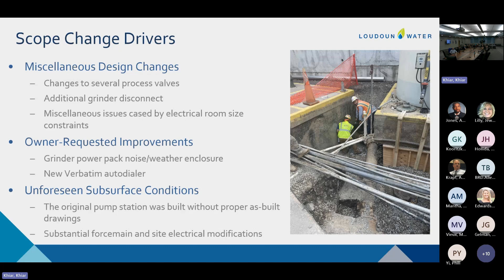To deal with this, in the case of the electrical conduit, we decided that for dealing with the issue of safety, capacity, and lack of adequate protection, the best solution would be to route from the interior panels and devices out along the retaining wall pictured in the back, hit new junction boxes, and go underground at the proper depth with proper bedding and routing, then hit the devices outside.